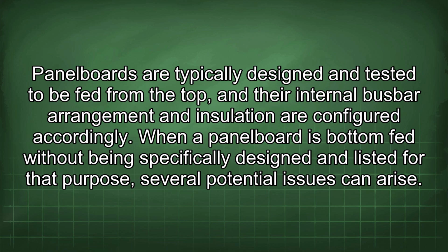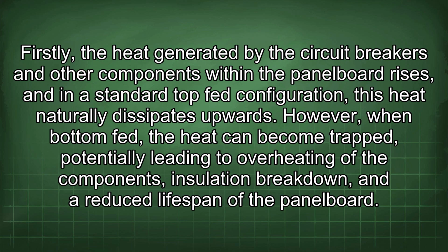issues can arise. Firstly, the heat generated by the circuit breakers and other components within the panel board rises, and in a standard top fed configuration, this heat naturally dissipates upwards. However, when bottom fed, the heat can become trapped, potentially leading to overheating of the components, insulation breakdown, and a reduced lifespan of the panel board.